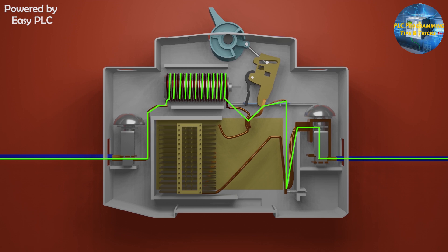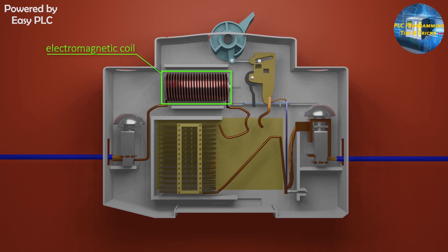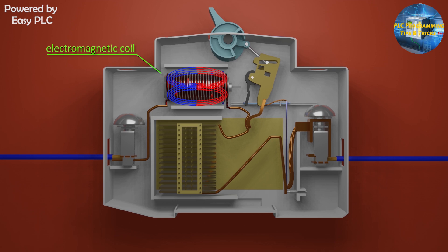Next, MCB have an electromagnetic coil. This coil acts as a safety device in case of any short circuit at the load side. Whenever the current is passing through the MCB it moves and passes through this electromagnetic coil. But this coil is designed in such a way that a very weak or less electromagnetic field is produced when the current passes through it within the range of the rated current of the MCB.